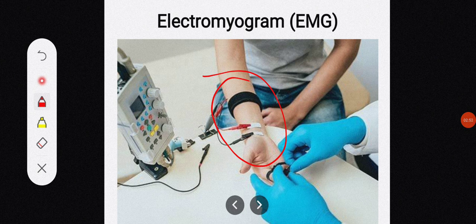If I'm trying to measure the EMG, that is the electromyogram, from smaller muscles, I will place a surface electrode on the surface of the body over that muscle. Now the property of a surface electrode is that it will pick up the bioelectric potentials near its range. So it is possible that it can pick up the bioelectric potential from the nearby larger muscles, which we do not actually need. We need the bioelectric potential from the smaller muscles. So this is the problem with the surface electrode. To overcome this problem, what is the solution? We can use needle electrodes that can be inserted directly into the muscle of interest.